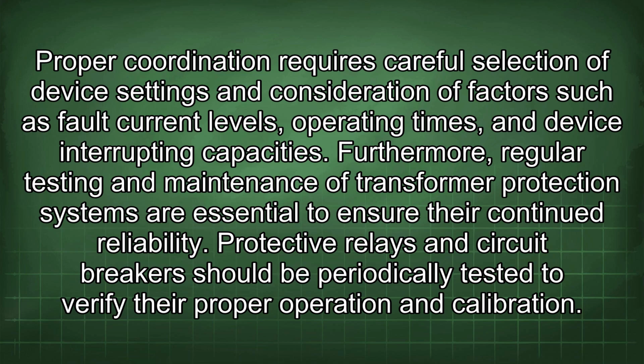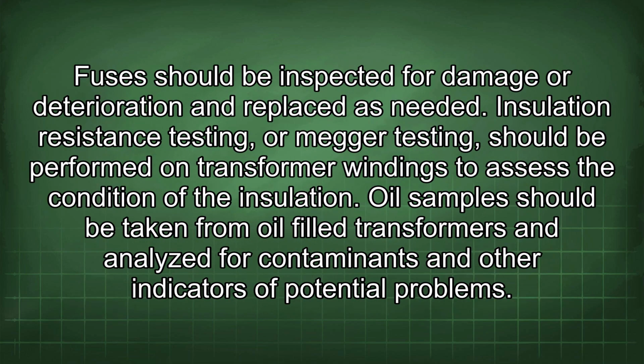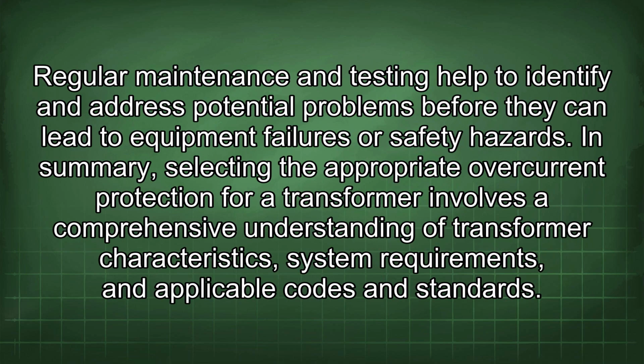Furthermore, regular testing and maintenance of transformer protection systems are essential to ensure their continued reliability. Protective relays and circuit breakers should be periodically tested to verify their proper operation and calibration. Fuses should be inspected for damage or deterioration and replaced as needed. Insulation resistance testing, or megger testing, should be performed on transformer windings to assess the condition of the insulation. Oil samples should be taken from oil-filled transformers and analyzed for contaminants and other indicators of potential problems.